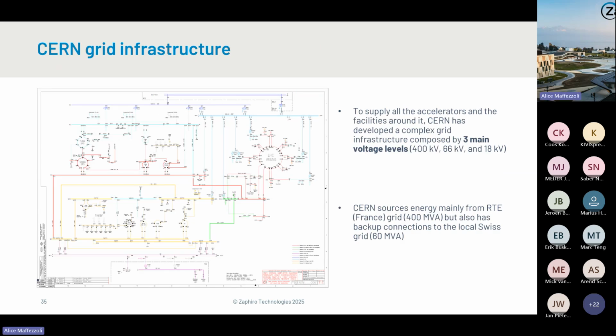Just to go a bit more into detail on the electrical part: here is represented the single line diagram of the electrical infrastructure. We can see the 3 different voltage levels described earlier, the 400 kV, mainly supplied by the French grid operator, with some critical loads backed up by the Swiss grid operator from the city of Geneva. Then a step down to 66 kV and a step down to 18 kV, and the LHC is supplied at 18 kV.